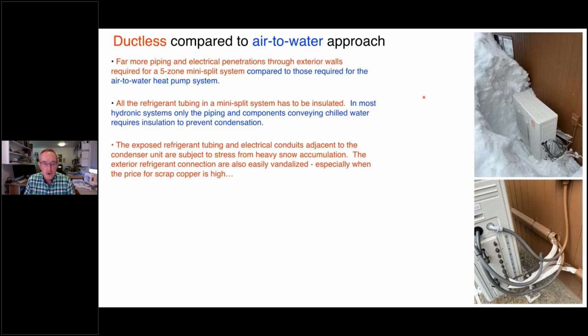Exposed refrigeration tubing and electrical conduits adjacent to the condenser. They're subject to stress from heavy snow. Now, that upper right photo, I took that photo because I had to shovel that unit out. It was actually on a church, and a combination of a very snowy winter plus people shoveling the roof and just allowing that snow to build up. That unit was completely buried in easily under 3 feet of snow.